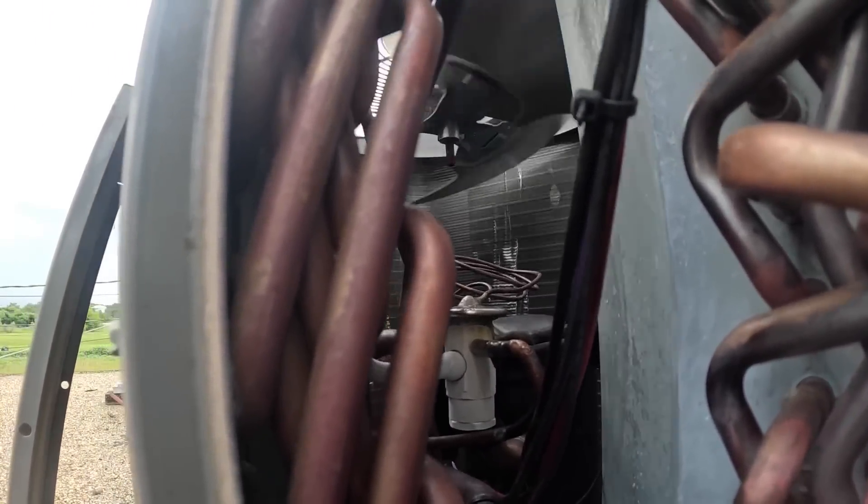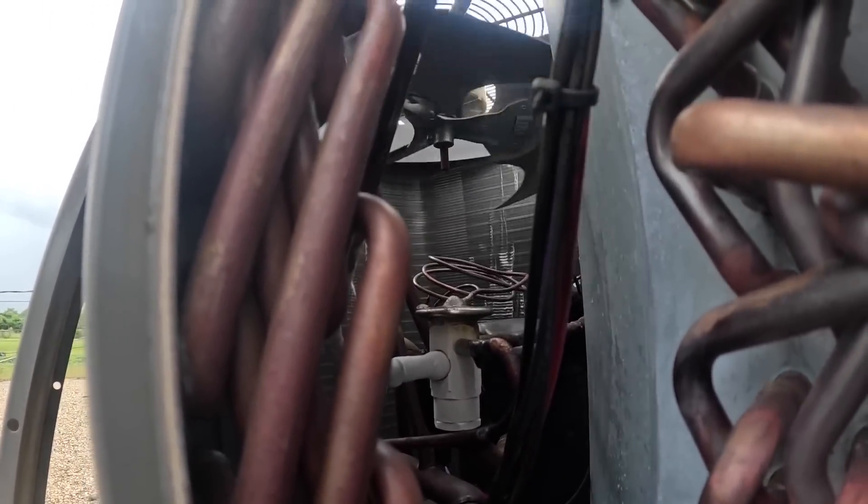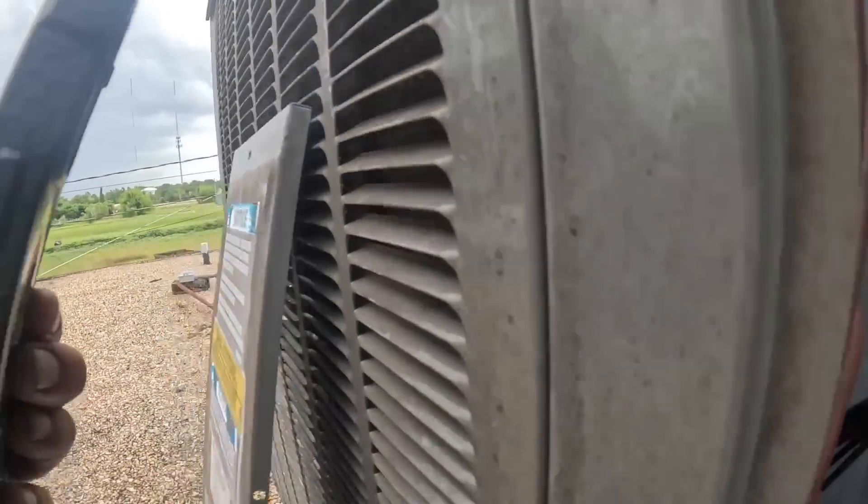And that is not a replaceable power head, so we've got to do this job again. I gotta look back and see how long it's been since I've done it, see if we can get the part under warranty. I did this TXV four months ago. I changed the dryer, I did everything just like you're supposed to, but here we are four months later and this TXV has failed again.